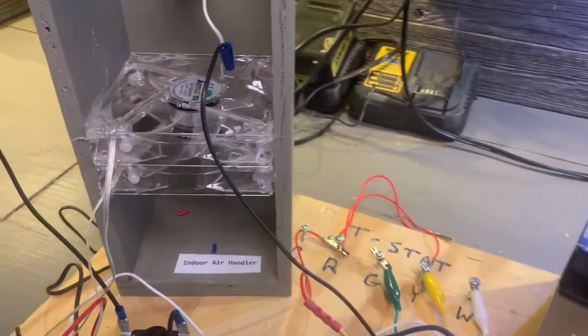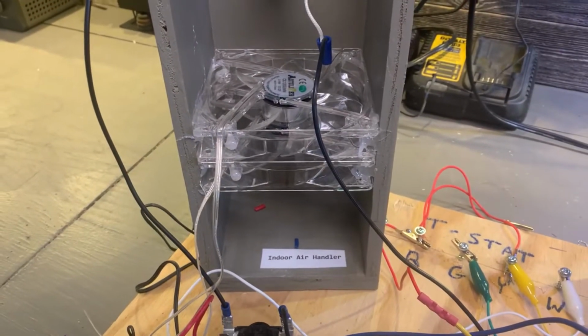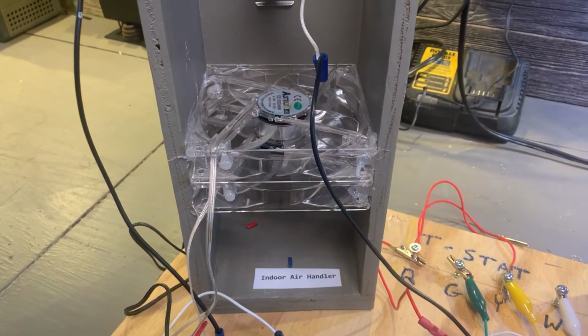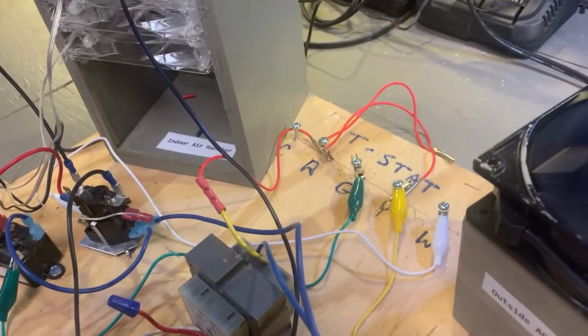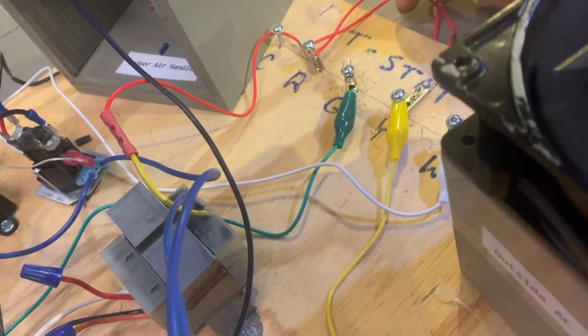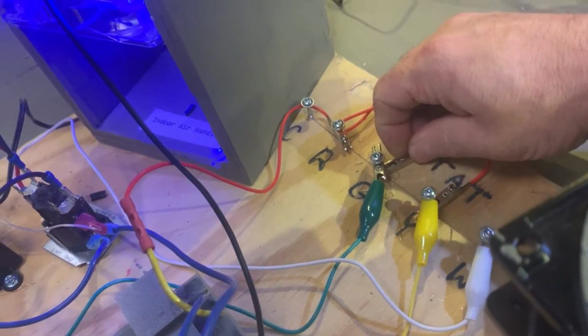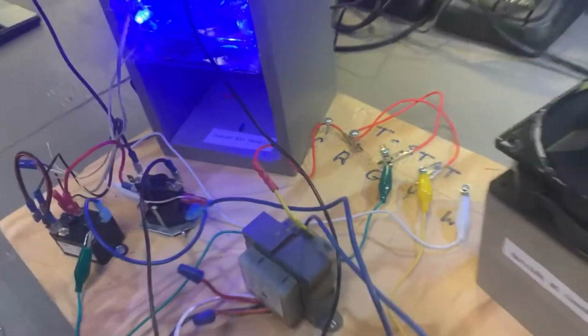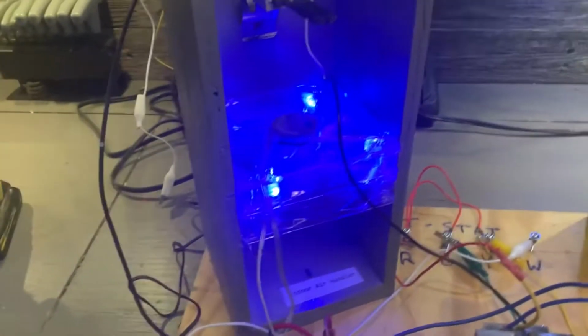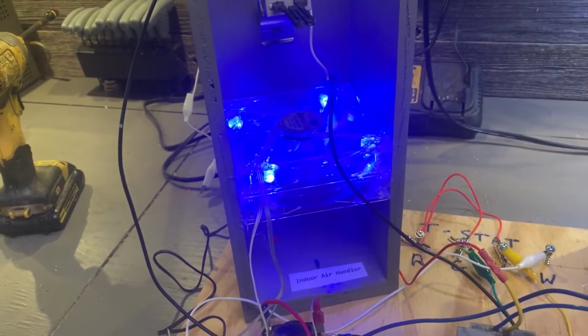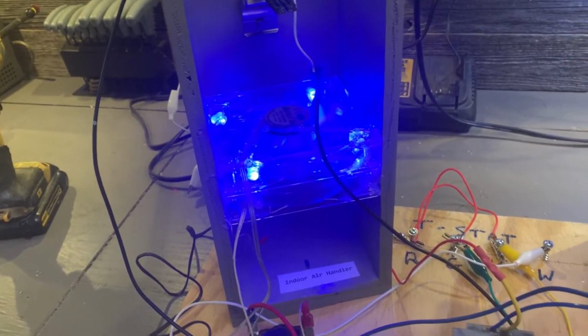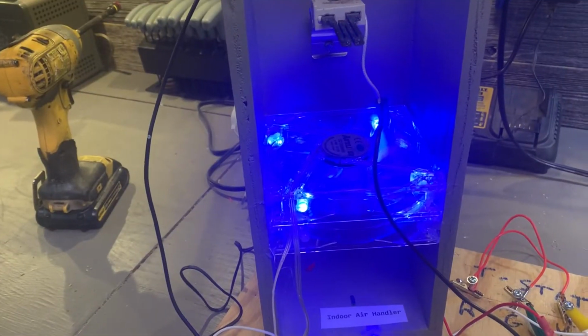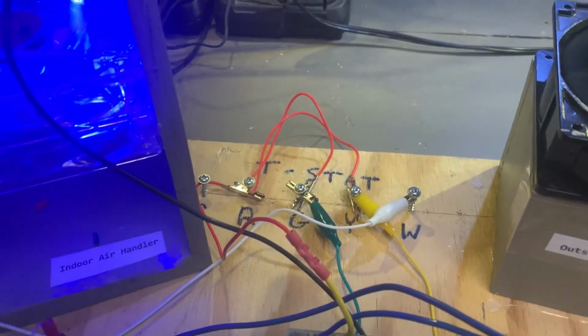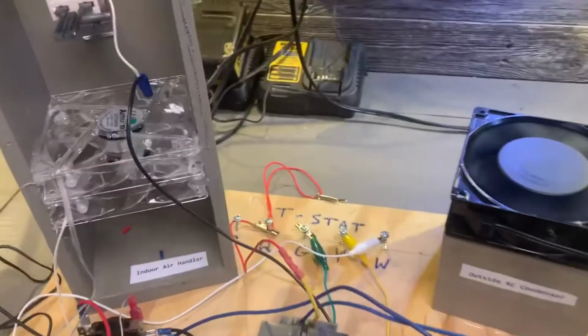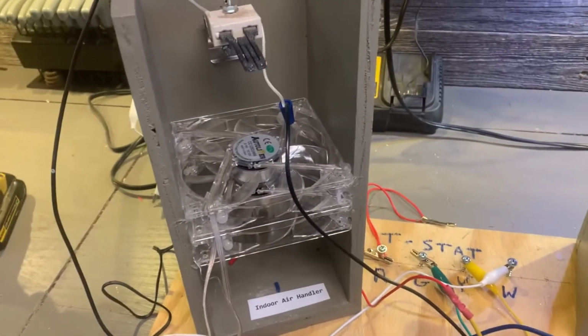The other thing that we need when we want air conditioning is we need a blower on the inside to move the air across the coils. So we're going to do that with our red to green. Anyway, I got the fans color coded, blue for cooling and red for heat. I thought that would be fun. We've got our little condenser on out here, the blue cooling speed. We'll go ahead and disconnect that now. Okay, I disconnected our fan and our other fan.